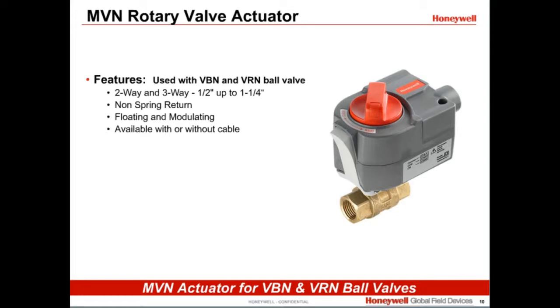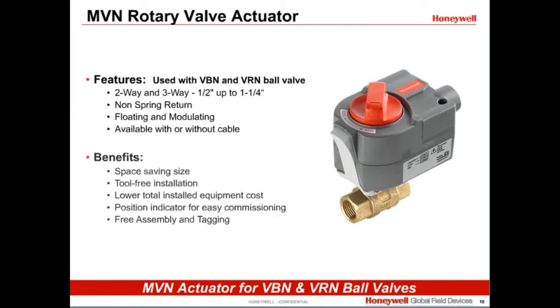The Honeywell VBN actuator is used exclusively with VBN valves from 1/2 up to 1 1/4 inches. It is available in floating and modulating non-spring return models. It fits in confined spaces and installs easily with no tools. Just click it into place. Not only does the MVN snap onto the valve, it also has a position indicator and a tag to identify it. MVN actuators are covered in detail in the Honeywell MVN actuator video, available on buildingcontrols.honeywell.com in the video library.